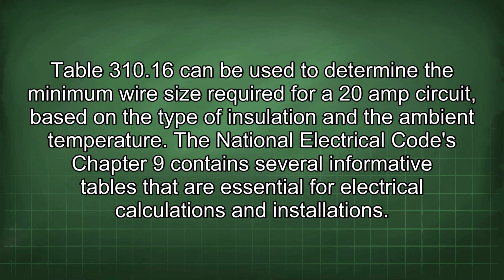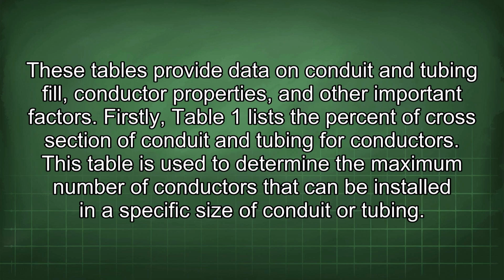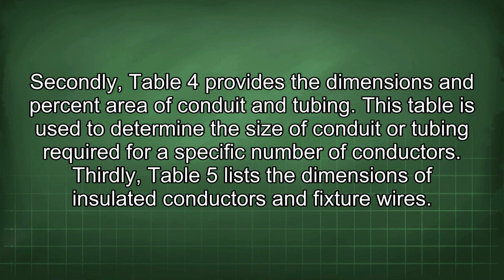The National Electrical Code's Chapter 9 contains several informative tables that are essential for electrical calculations and installations. These tables provide data on conduit and tubing fill, conductor properties, and other important factors. Firstly, Table 1 lists the percent of cross-section of conduit and tubing for conductors. This table is used to determine the maximum number of conductors that can be installed in a specific size of conduit or tubing. Secondly, Table 4 provides the dimensions and percent area of conduit and tubing.